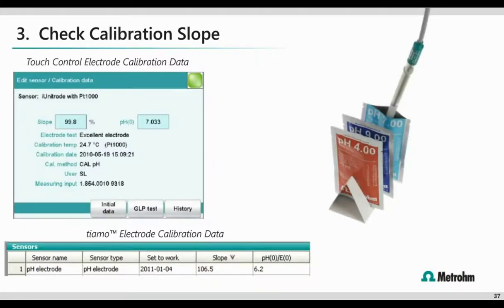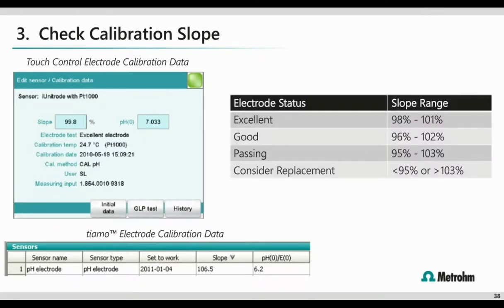Okay. Thirdly, check the calibration slope. Remember, a good calibration slope is necessary to correlating the correct pH value to the millivolt signal of the electrode. If you're uncertain if your electrode is past retirement, perform a quick calibration and take a look at the calibration slope. Consider replacing your electrode if your slope is consistently lower than 95% or higher than 103%.